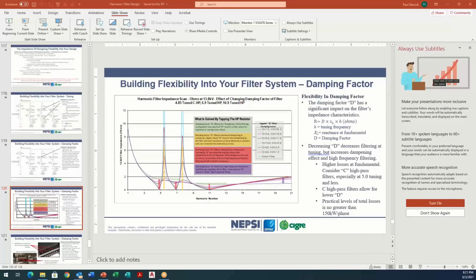One of the things to remember about filter design is that if you go with a very small kVAR, a lot of times it becomes much more critical that you get the filter design exactly right. Say you have a 30 megawatt or 100 megawatt system. If I put a 100 kVAR filter in, you could tune it exactly in your program and probably get it to look right. But the reality is it's just a sliver of a filter in the impedance scan, and it's not going to perform out in the field because of various things in the filter.